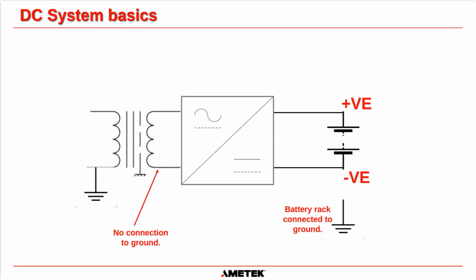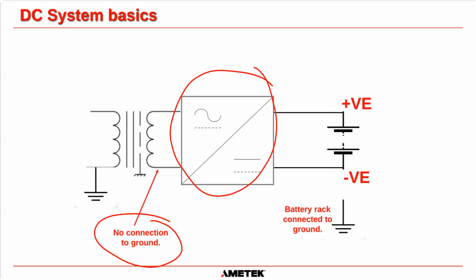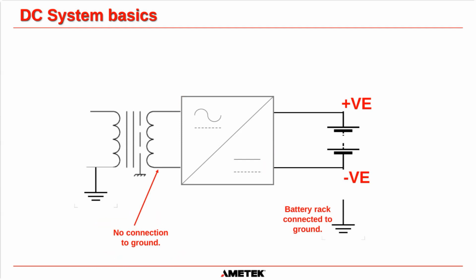Okay, so this is the exact picture that I just showed you on the left-hand side. There is a transformer, okay? We are floating. Now all we're doing on this picture is adding a charger, or a rectifier, onto that separately derived secondary transformer, okay? Remember, there is no connection to ground. And then we've also connected a battery on the output of that charger, in parallel with the charger. The battery usually sits on a rack, and that rack is metallic.